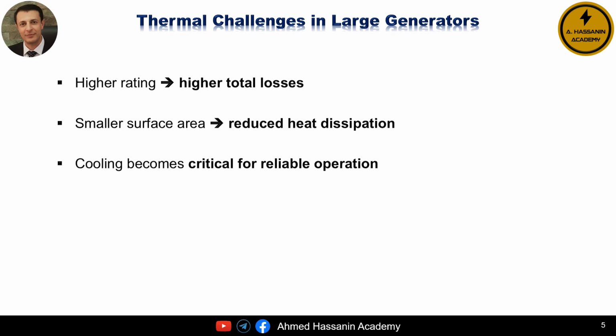So we end up with a situation where more heat is being generated, but it has fewer paths to leave the machine. If this heat is not removed efficiently, temperatures rise, insulation degrades, and reliability is affected. That's why, for large synchronous generators, cooling is not an optional feature. It's a core part of the design. Proper cooling ensures stable operation, long insulation life, and safe continuous operation under high load conditions.